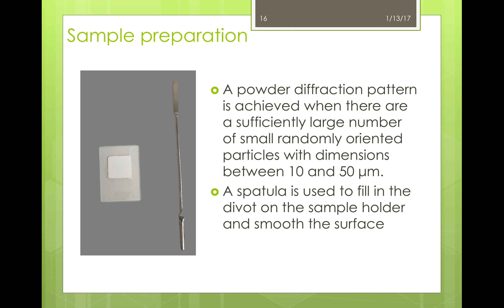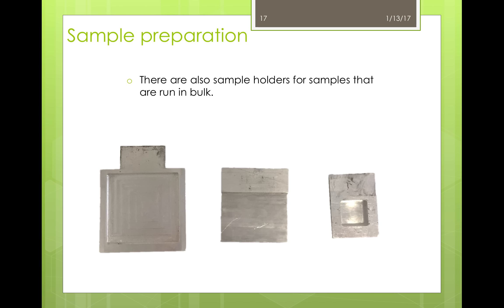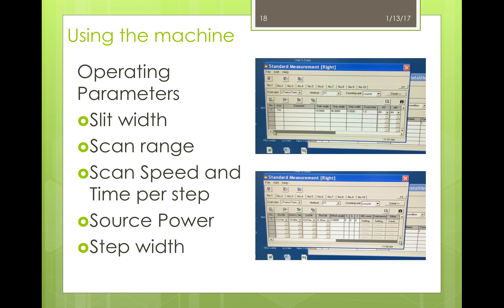For powder diffraction, the size of the particles should be between 10 and 50 microns. The powder is packed into a sample holder using a spatula to ensure that the divot in a glass slide is filled and the surface is as smooth as possible. If you're doing more of a bulk sample, there are holders for that as well. There are many parameters that need to be set to determine how well your data collection will go. These parameters have to do with the characteristics of the equipment, such as the slit width, the settings of the power source, how the rotation is controlled, and how the data is collected. It is best to read articles related to your project for a guideline when deciding how to control these parameters for your sample.